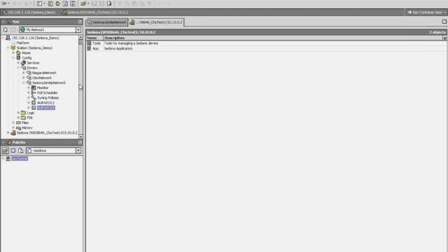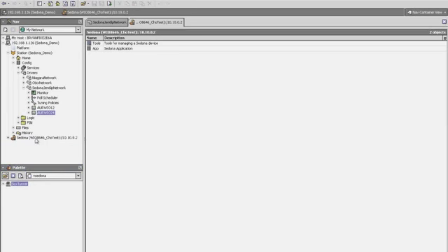So you enter into a SOX tunnel session, and there you can see the Sedona controller, WIO8646, which is the naming convention for our 24IO controller, for the 8 universal inputs, 6 analog outputs, 4 digital inputs, and 6 relay outputs. So if you drop down the plus sign beside the Sedona device, you can see you have two folders, Tools and App.